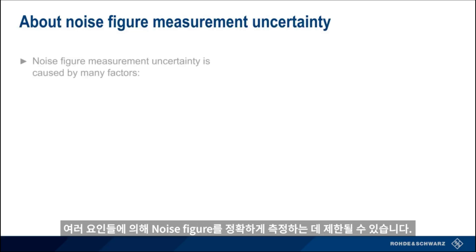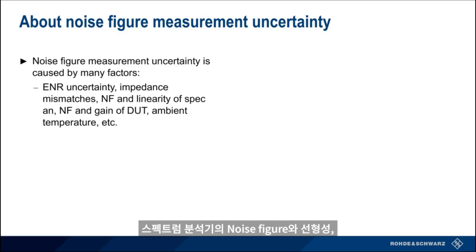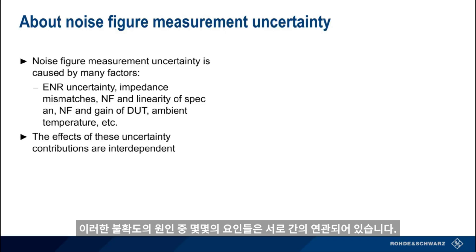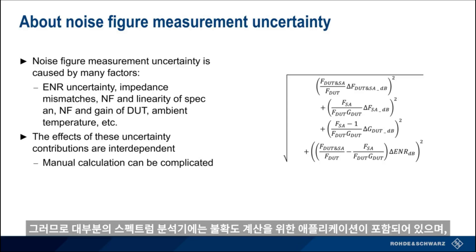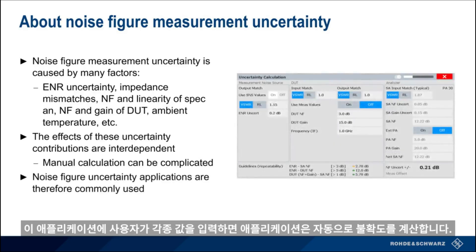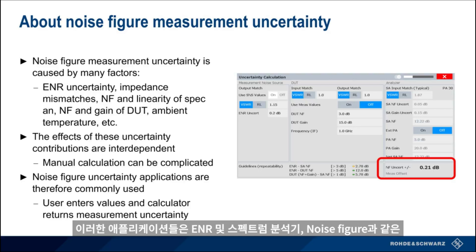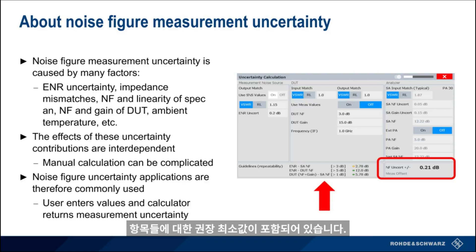Our ability to accurately measure noise figure is limited by many different factors — for example, the uncertainty of the ENR values of our noise source, impedance mismatches between the source, DUT, and analyzer, the spectrum analyzer's noise figure and linearity, the DUT's noise figure and gain, the ambient temperature, etc. Some of these sources of uncertainty are also mutually dependent. The manual calculation of uncertainty can be somewhat complicated, and therefore most spectrum analyzers also include an uncertainty calculator application, in which the user enters various values and the application automatically calculates and returns the measurement uncertainty. These applications often also include guidelines regarding recommended minimum values for things such as source ENR or spectrum analyzer noise figure.